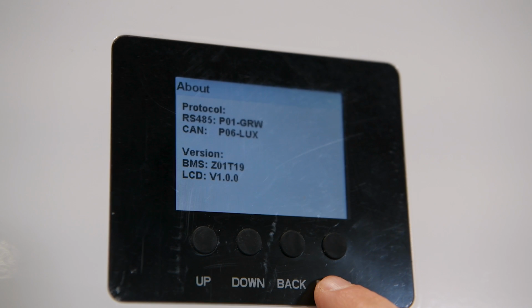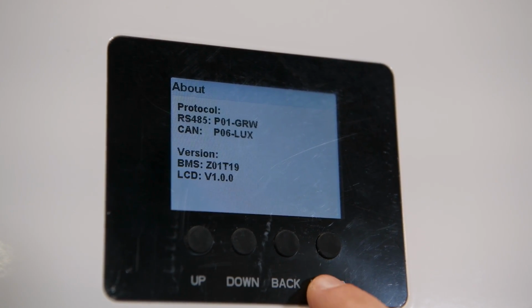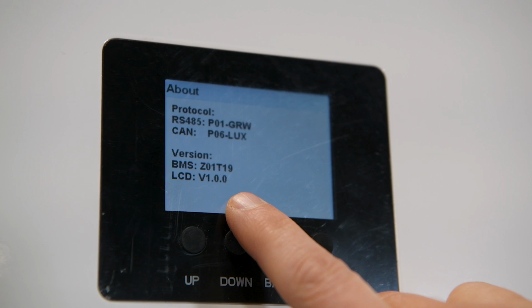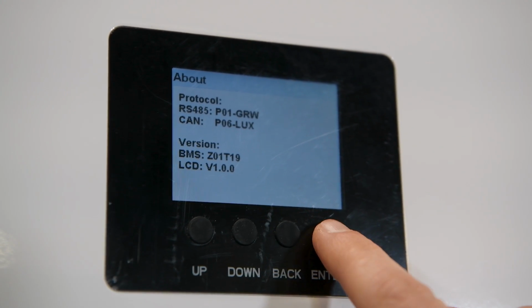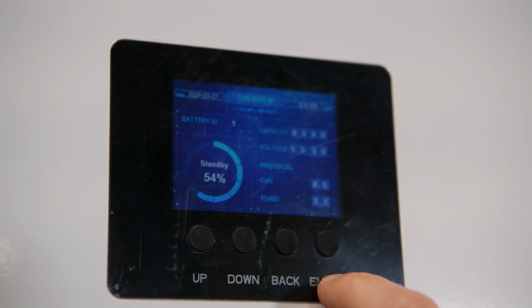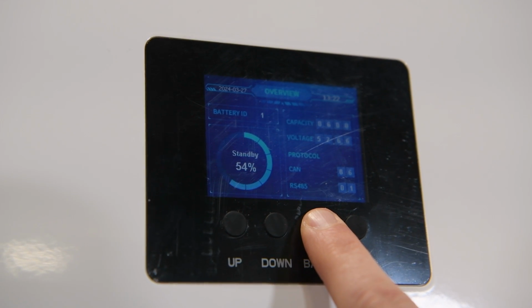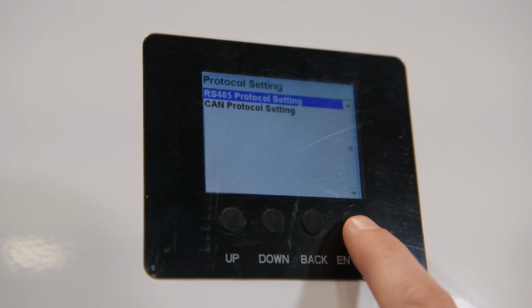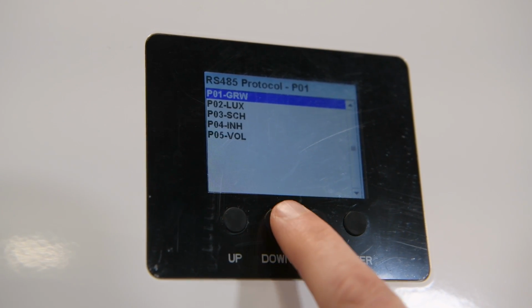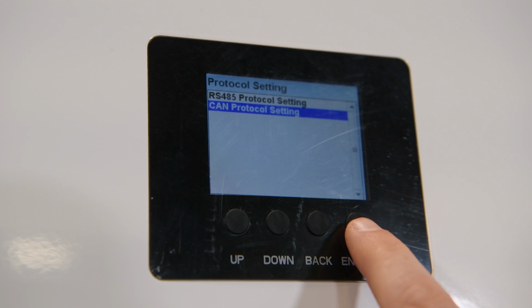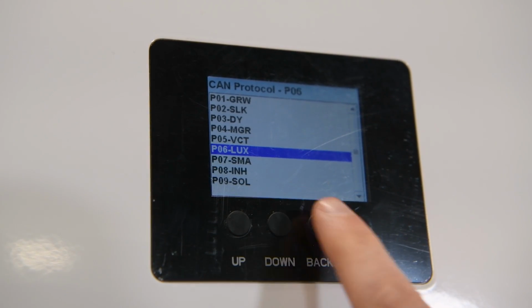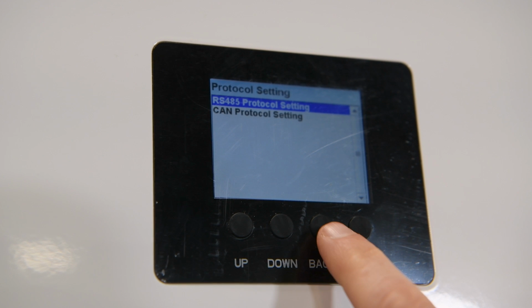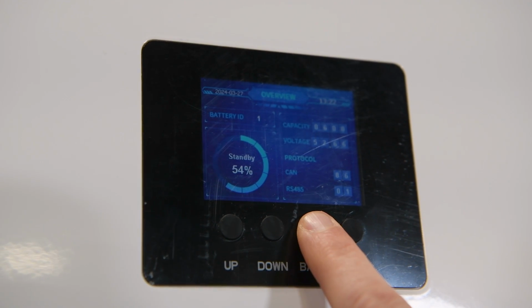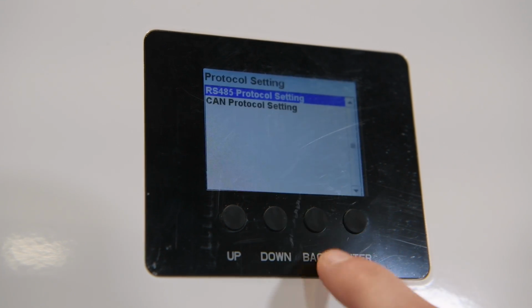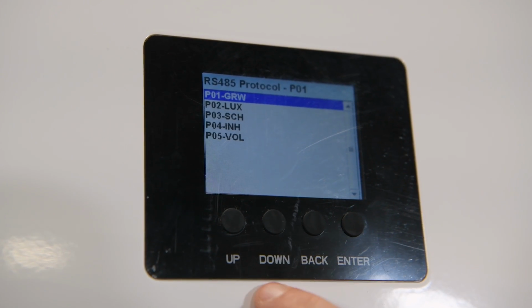Next, hit the back button to navigate to the About screen. Here you'll find information on the currently selected RS-485 CAN protocol, as well as the current versions of the BMS and screen firmware. After reviewing, press Enter to return to the main screen. Press and hold the back button for approximately 5 seconds, then release it to access the protocol setting menu. Once there, utilize the up and down buttons to move through the options within the protocol setting menu. When you've highlighted your choice, press Enter to select and enter either the RS-485 or CAN protocol menu, depending on your setup needs. We are actually going to set up both for the 18K. Use the up and down buttons to navigate the RS-485 CAN protocol menus and press Enter to select the highlighted protocol.